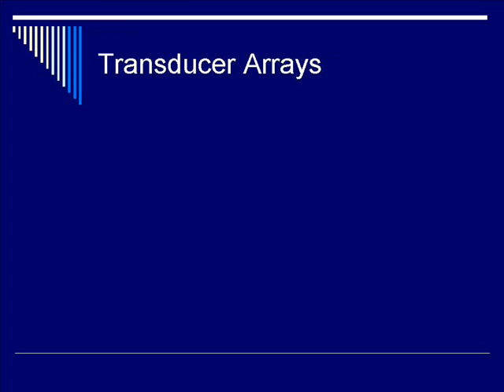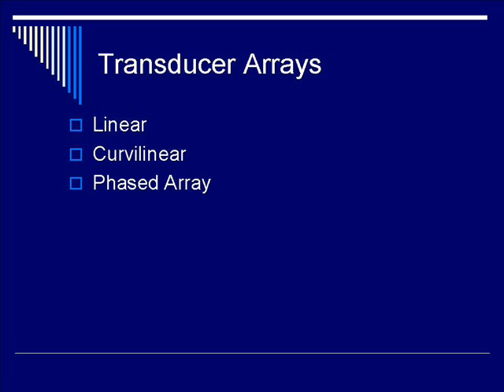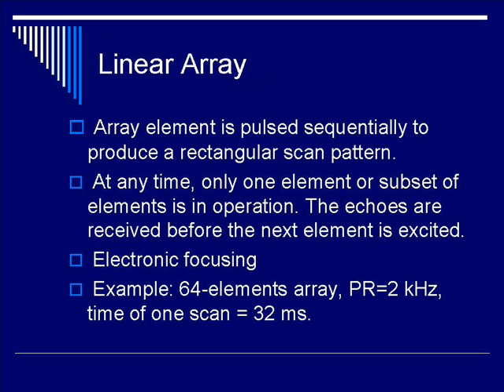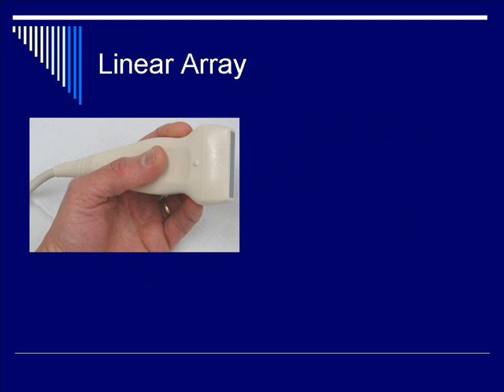So far we've been talking about single element focused or non-focused transducers. Let's move on to transducer arrays, which could be linear, curvilinear, phased array, or mechanical. A linear array consists of multiple transducer elements that are pulsed sequentially to produce a rectangular scan pattern. At any one time, only one element or subset of elements is in operation. The echoes are received before the next element is excited. Focusing is done electronically. An example is a 64-element array with a pulse repetition rate of 2 kHz.